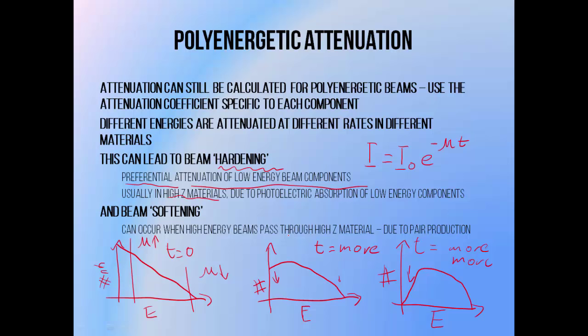The inverse can also occur when a very high-energy beam passes through a very high atomic number material — this is known as beam softening. When very high-energy beams pass through high atomic number materials, the pair production effect becomes more likely, so the higher-energy part of the spectrum becomes more likely to interact than the lower-energy parts. When a beam's average energy is increased via filtration, it's said to be hardened; when decreased, it's said to be softened. Hard equals high energy, soft equals low energy.